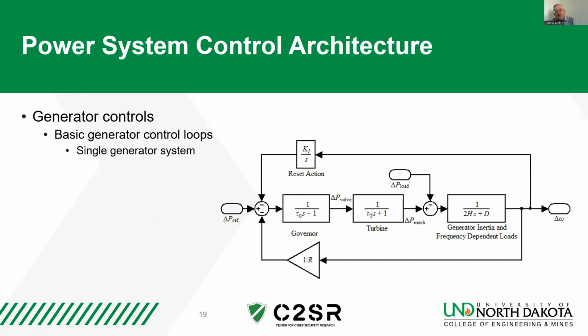Basic generator controls, we put these things together. This is quite appropriate for everything from a standby generator inside an industrial facility all the way up to a single generation utility. Great when you have a set point that you want to control, make sure you have the right frequency, and as loads change, the generator and its governor are able to respond.